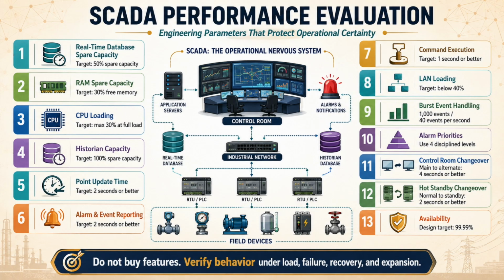The first engineering parameter is real-time database spare capacity, because the real-time database is the live nervous system of the SCADA environment, carrying process variables, equipment status, alarm states, calculated values, communication health, command feedback, quality indicators, interlocks, diagnostics, and derived operational logic. If present operation requires 40,000 live points, the design should not be built around a 45,000 point architecture and called optimized, because that is not optimization, that is fragility disguised as efficiency.